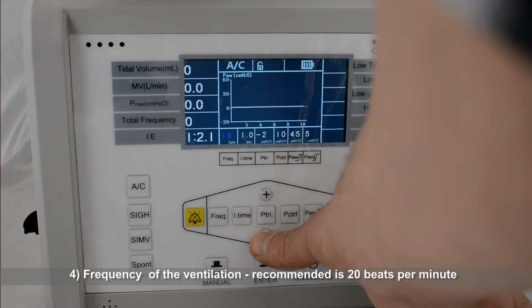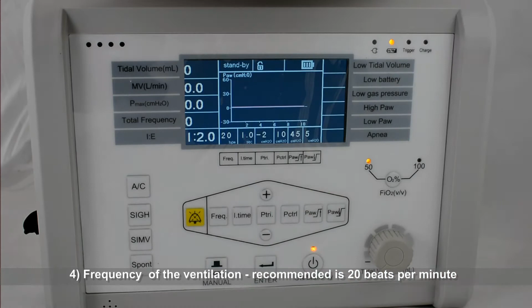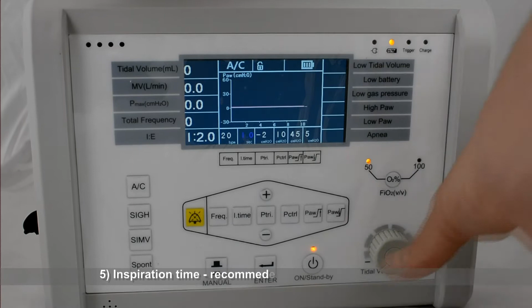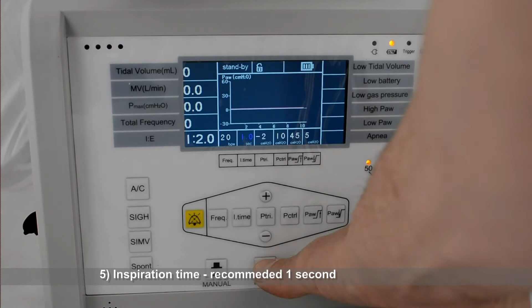Frequency. The recommended value is 20 breaths per minute. We confirm by pressing enter. Then we go to inspiration time. The recommended value is 1 second, but we can change it. Then we confirm.